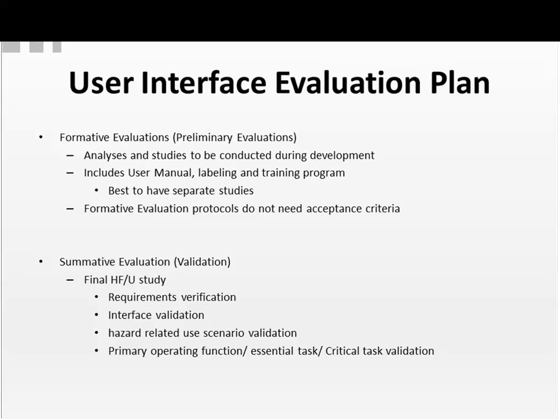The summative evaluation, the validation, is the final human factors study. As part of it, you do requirements verification, you do an interface validation, and you validate the hazard-related use scenarios. You validate the primary operating functions, the essential tasks, and the critical tasks that we've defined before. In this case, for validation, you do need acceptance criteria.